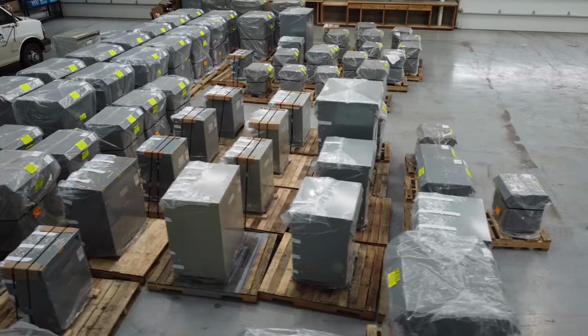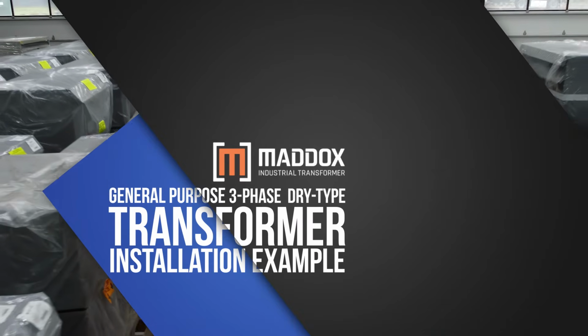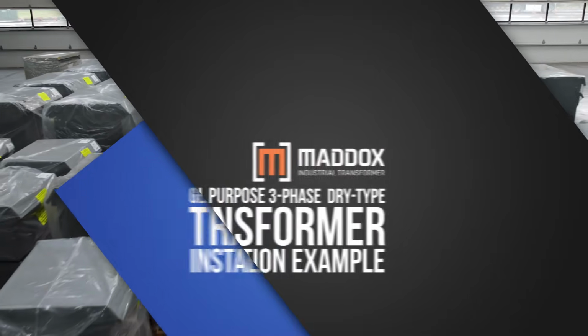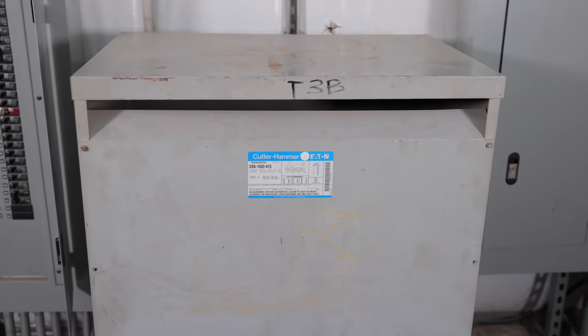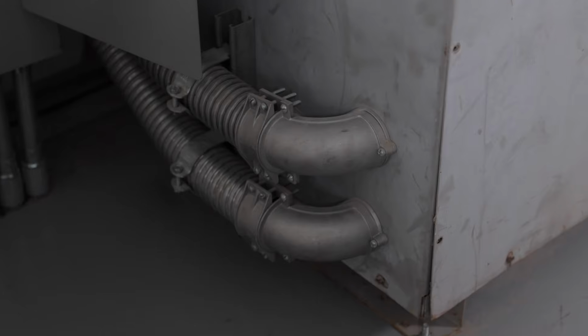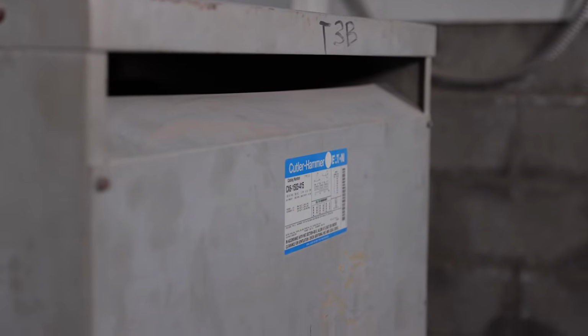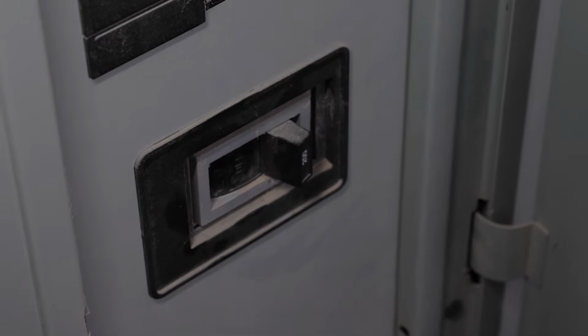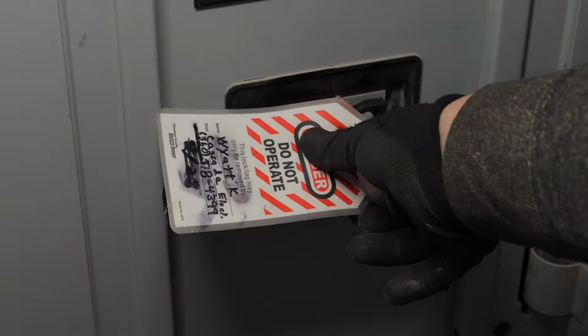The following is an example of the removal and installation of a new three-phase general-purpose dry-type transformer. This old transformer was past its prime and had developed a loud buzzing noise and needed replacing. First, the electrician turns off the power and locks out the breaker feeding the transformer.